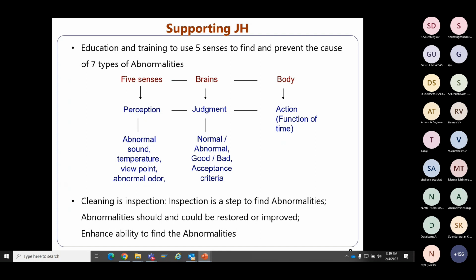Put simply, if I hear a noise from this part, I judge whether it is normal or abnormal. If I touch this part and sense some vibration, I judge whether that vibration is normal or abnormal. If I touch a motor's cooling fins, I judge whether the temperature is normal or abnormal. And if I see the motor current from the transducer, I check whether the current is normal or abnormal. Based on the kilowatt rating of the motor, there will obviously be a standard no-load current and full-load current marked therein.